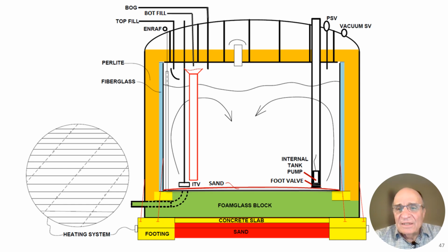Now, how do you fill the tanks? Well, before we fill the tank, let's talk about another type of pump that's common to tanks, and that's an internal tank pump. Internal tank pumps are installed in a tube that goes from the top of the tank down to the bottom of the tank, and it has what's called a foot valve on the bottom, so that when the pump is lowered, it opens the foot valve. When you remove the pump, it closes the foot valve. And these internal pumps can be turned on electrically. There's an electric wire that goes up to the top, and it pressurizes this tube, and then a pipe is connected from this tube to your vaporizers, and from there the LNG is pumped to the vaporizer.